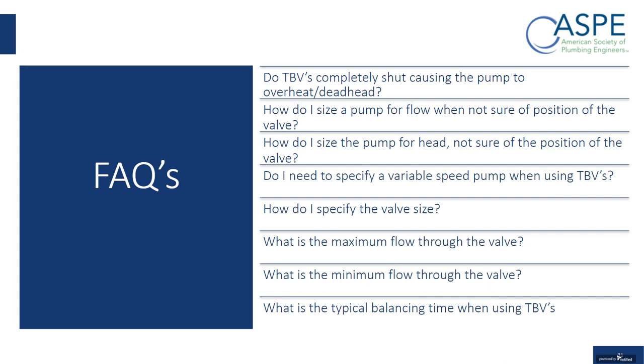And then when you have to size the pump for head pressure, you're not sure of the position of the valve. You basically go to the design CV, which I said is 5 degrees less than your return temperature, and use that CV to determine, for the given flow you need to offset the heat loss, what that pressure drop across the valve is. And that's how you would size the pump.